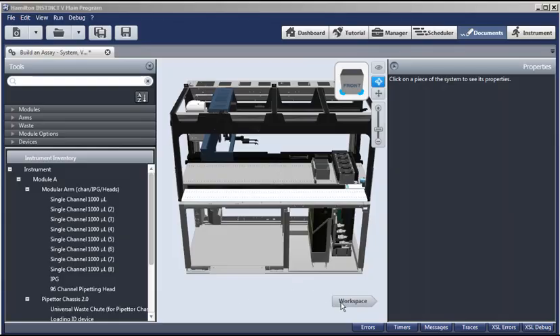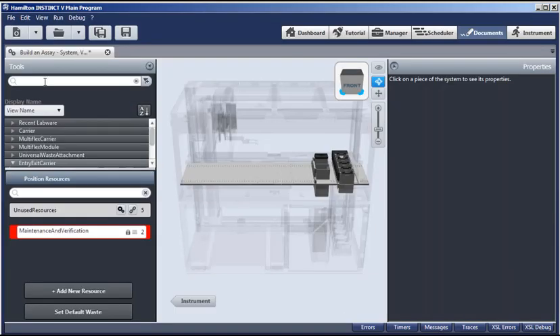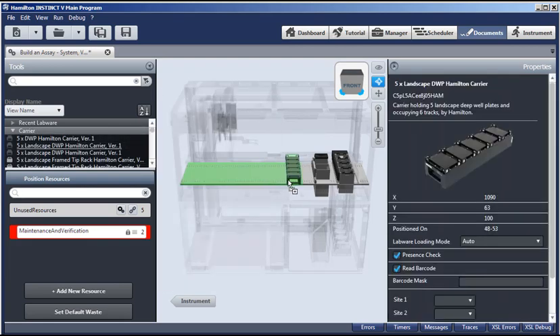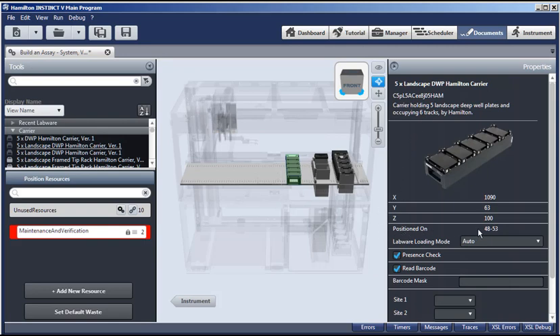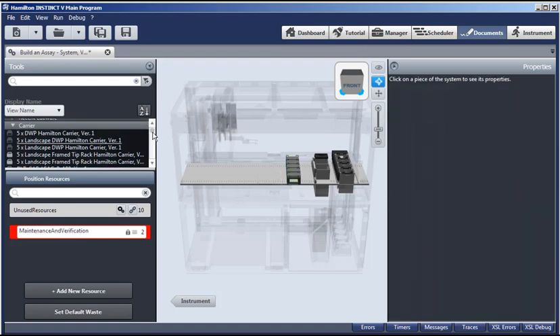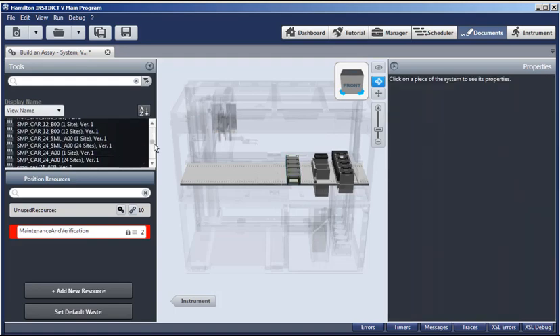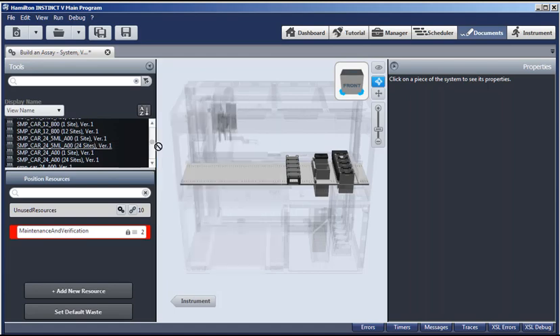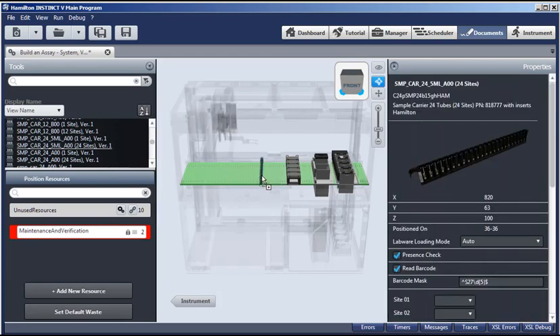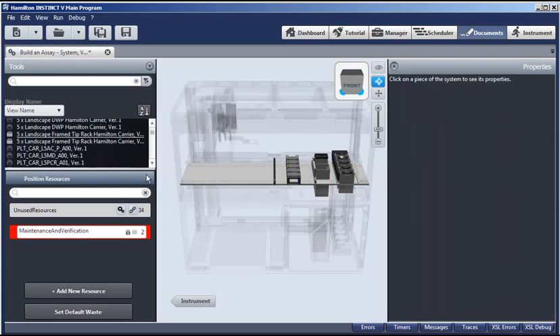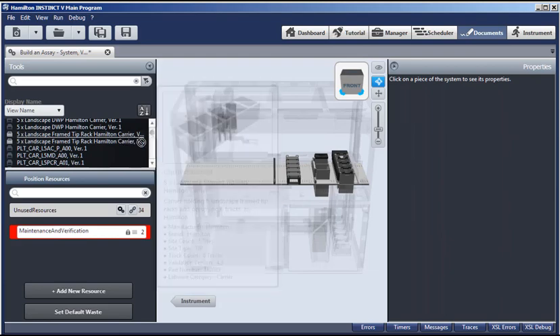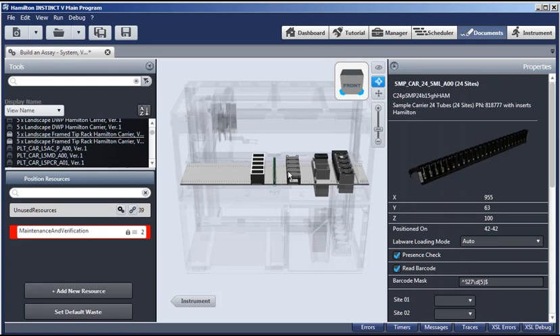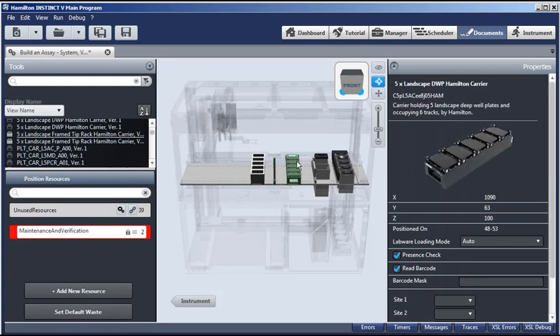Let's click the workspace toggle button. And here in the set of tools, we can select labware items and other modules. Let's begin from the list by selecting a plate carrier and placing it at a convenient location. It's a five landscape deep well carrier with six tracks. And the position of the tracks are shown right here. And there are other settings you can choose. And now we can select a 24 tube carrier. Place it by simply dragging and dropping. And a carrier for tips. Keep the mouse button held down and place it. And now we have a carrier for tips, a 24 tube carrier, which will be our source, and a carrier where we will place the 96 deep well plate, which will be our target.